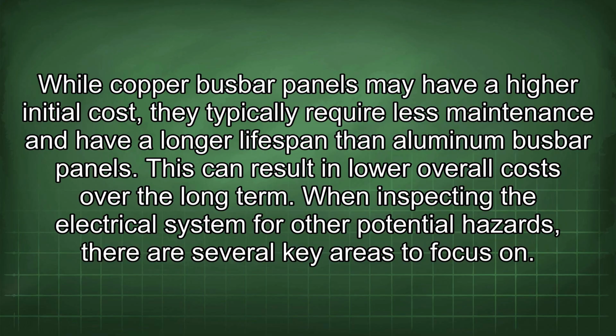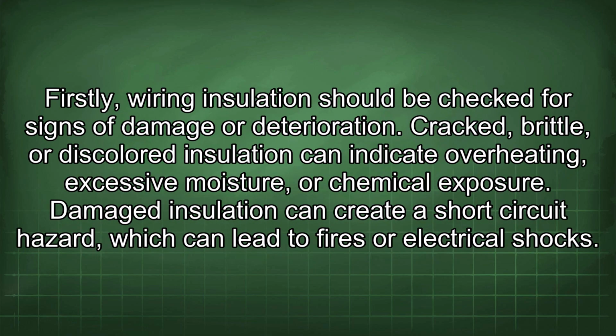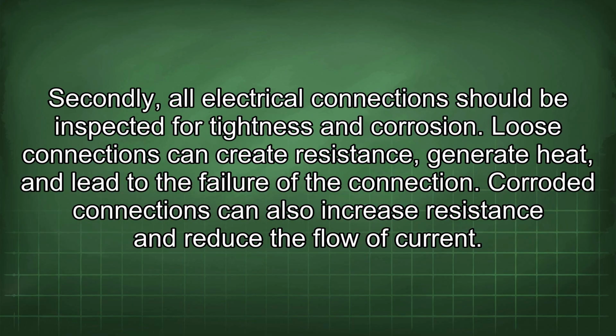When inspecting the electrical system for other potential hazards, there are several key areas to focus on. Firstly, wiring insulation should be checked for signs of damage or deterioration. Cracked, brittle, or discolored insulation can indicate overheating, excessive moisture, or chemical exposure. Damaged insulation can create a short-circuit hazard, which can lead to fires or electrical shocks. Secondly, all electrical connections should be inspected for tightness and corrosion. Loose connections can create resistance, generate heat, and lead to the failure of the connection. Corroded connections can also increase resistance and reduce the flow of current.